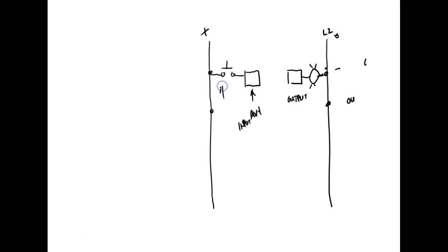Okay. Now if this is plus, then this input device is called sourcing. But the PLC's got to supply the what? To get current flow, what do we have? Current in DC, if we've got a positive, to get current flow I've got to have a negative. Okay, so this guy over here, inside on the PLC, would be connected to a negative. So now I've got current flow. So if my input devices are sourcing, then the input port has got to be connected to the sinking.